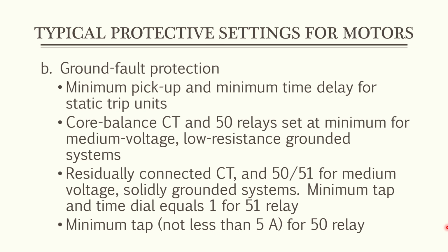B. Ground fault protection. The minimum pickup and minimum time delay for static trip units, core balance CT, and 50 relays set at minimum for medium voltage, low resistance grounded system. Residually connected CT and 50 over 51 for medium voltage, solidly grounded systems. Minimum tap and time dial equals 1 for 51 relay. Minimum tap not less than 5 amperes for 50 relay.